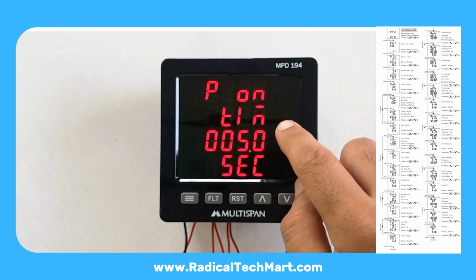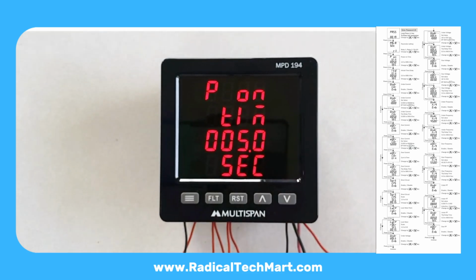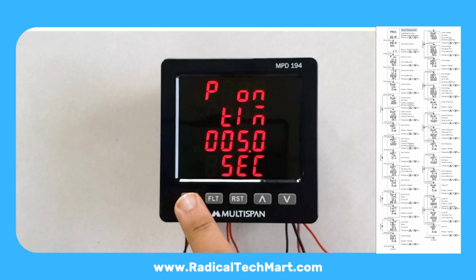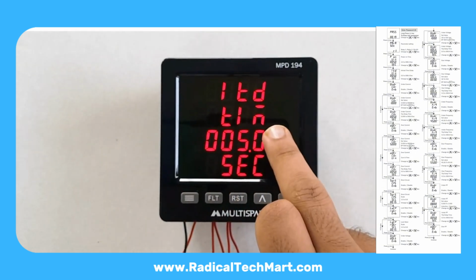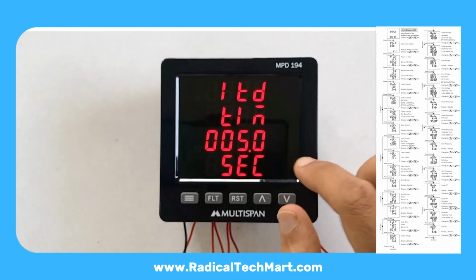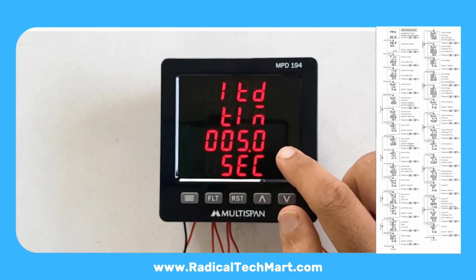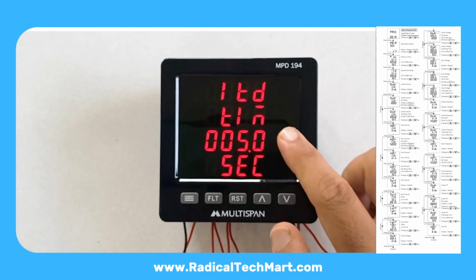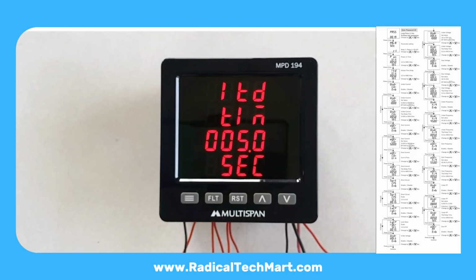First screen, power on delay, default 5 seconds. This is the delay after power is applied before protection becomes active. Press set. Next, initial time delay, ITD, default 5 seconds. This delay works after current starts flowing. For example, in star-delta starters, starting current is high for a few seconds. You can set ITD slightly higher than your star-delta changeover time so that no trip occurs during starting.